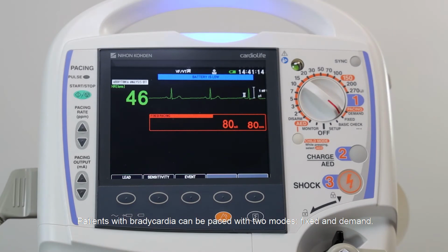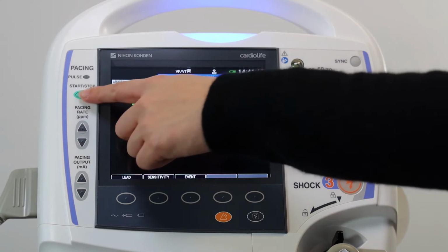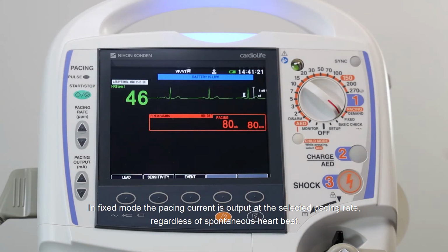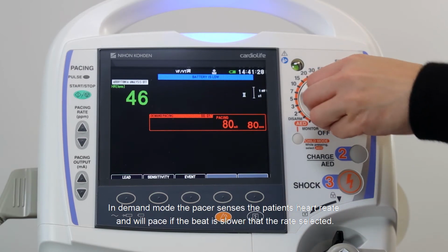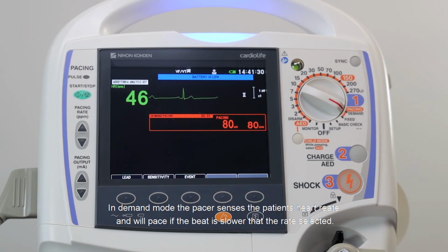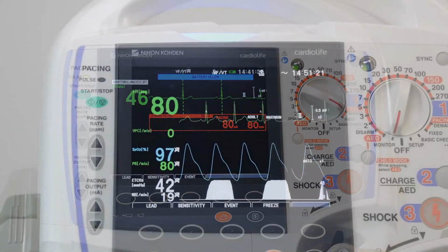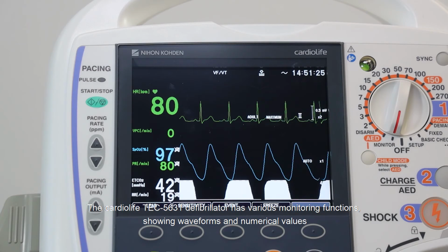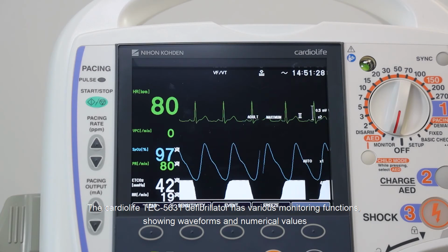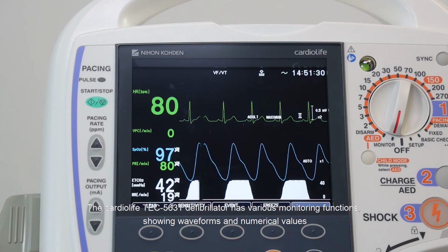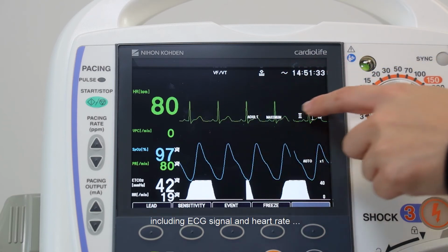Patients with bradycardia can be paced with 2 modes, fixed and demand. In fixed mode, the pacing current is output at a selected pacing rate, regardless of spontaneous heartbeat. In demand mode, the pacer senses the patient's heart rate and will pace if the beat is slower than the actual rate selected.